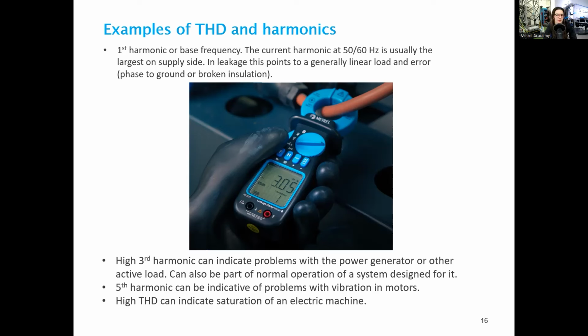Unexpectedly high THD can indicate the saturation of an electric machine, but it has to be mentioned that in systems with high presence of semiconductor solutions or consumers, the THD can be very high by default. Then we have higher harmonics. If they happen unexpectedly, they can mean that we have some semiconductors that are clipping, so we have unexpected square waves in the system, or they can mean problems with some very specialized equipment.